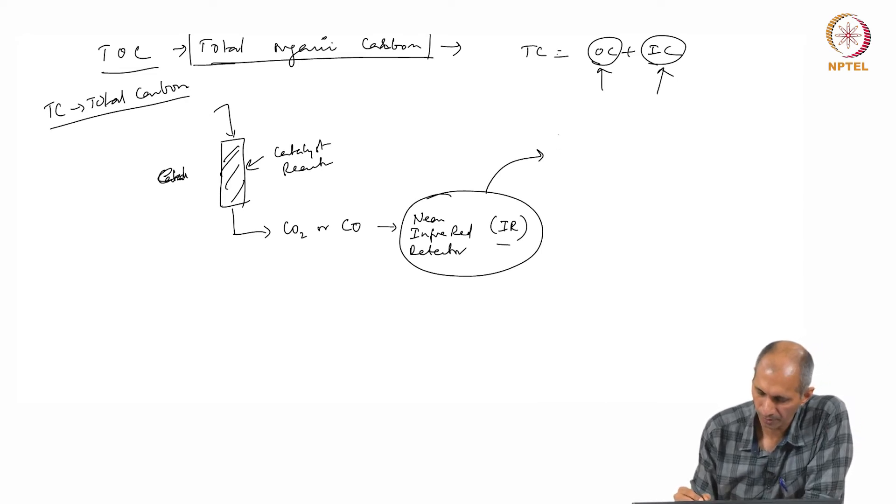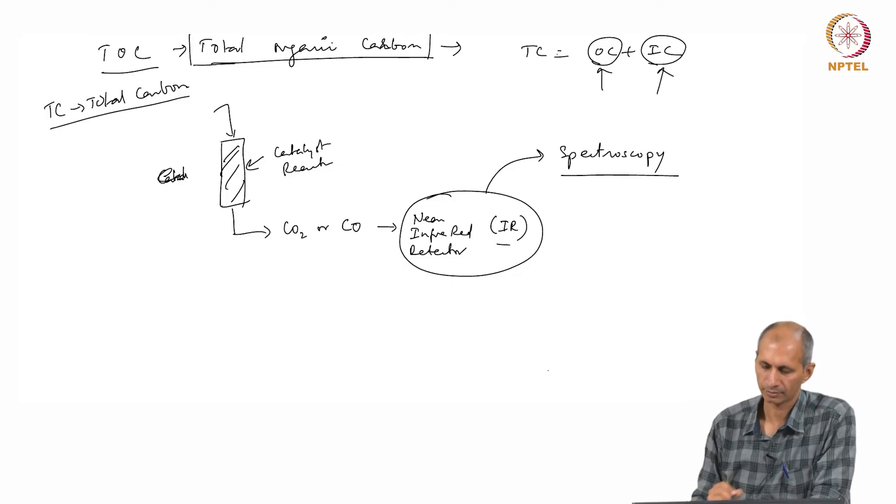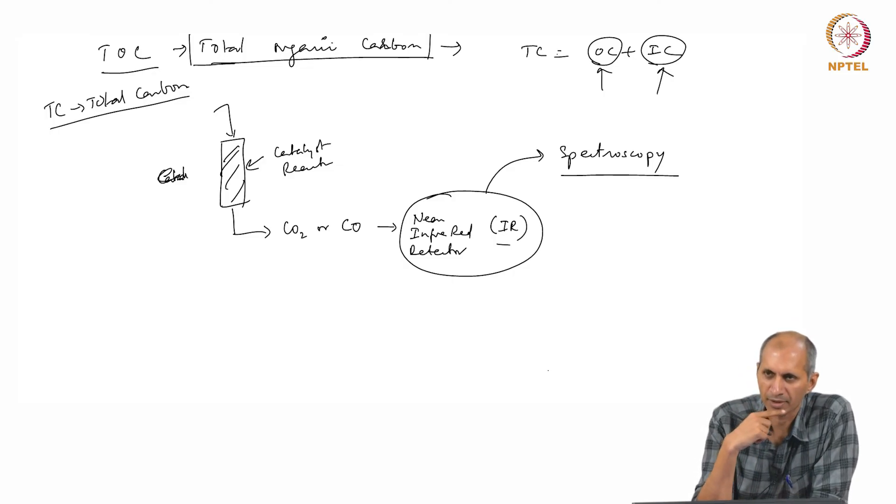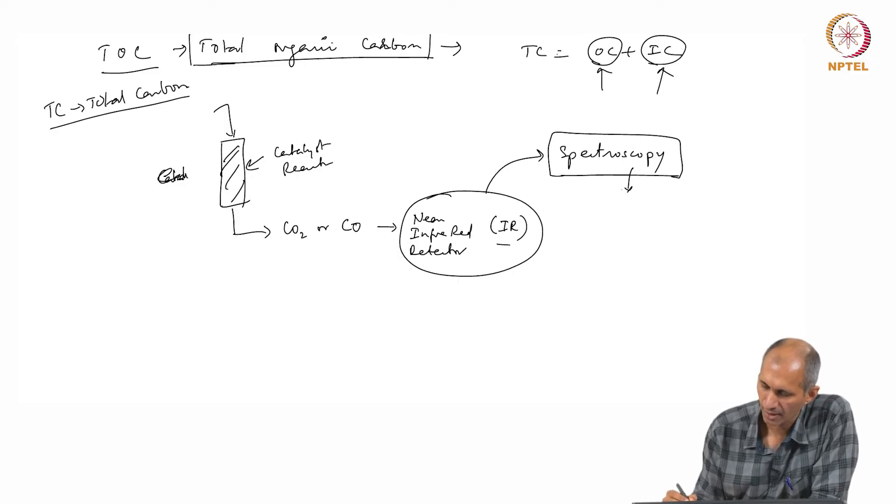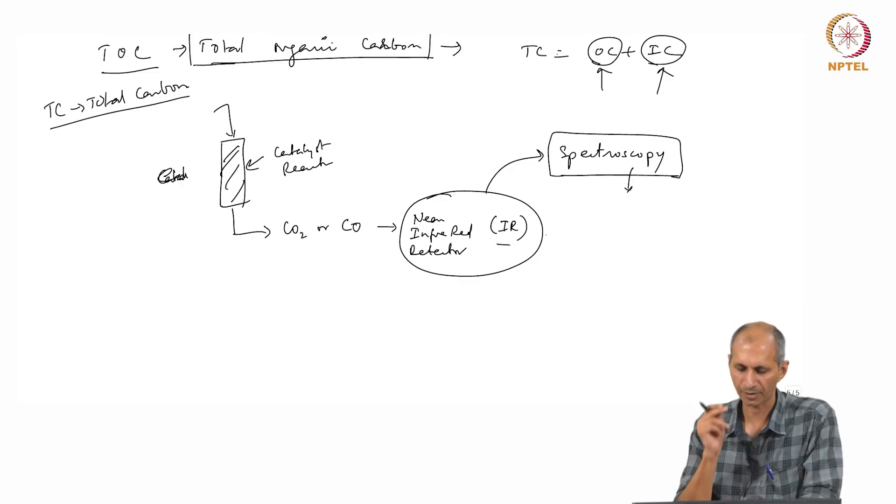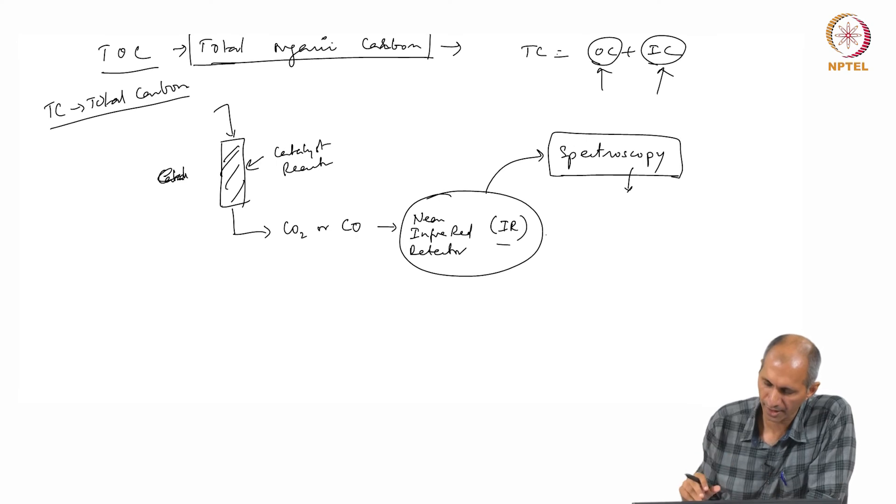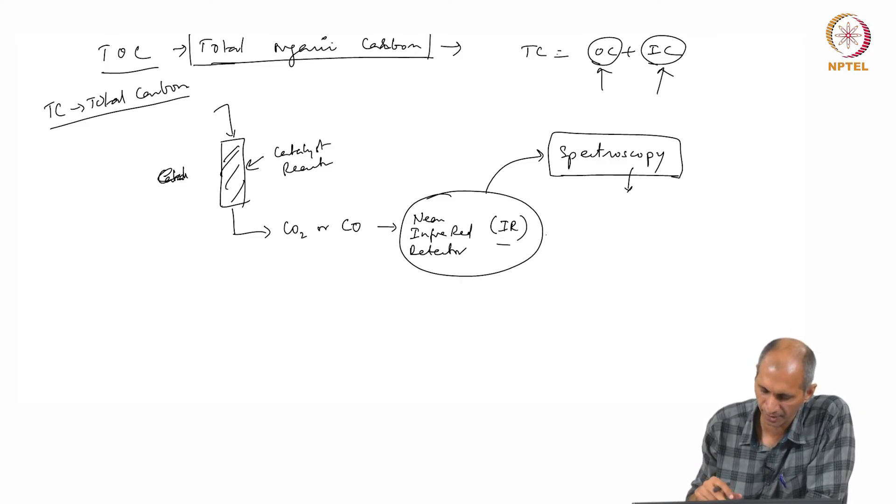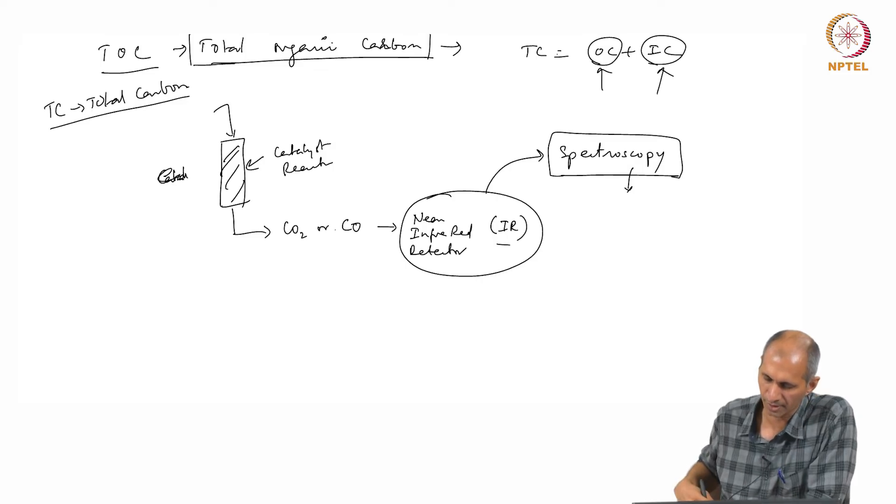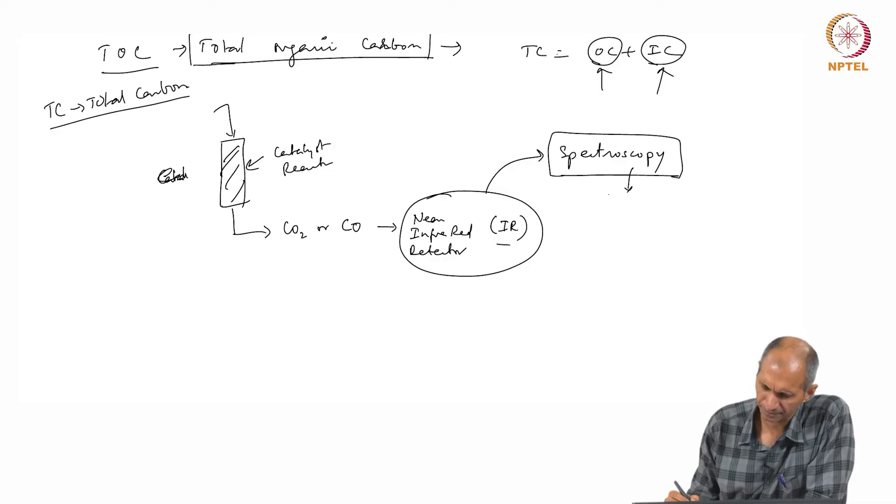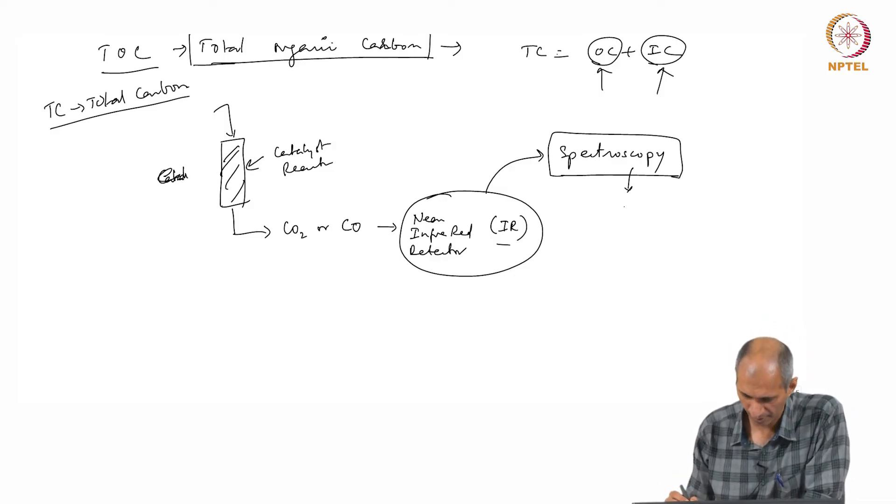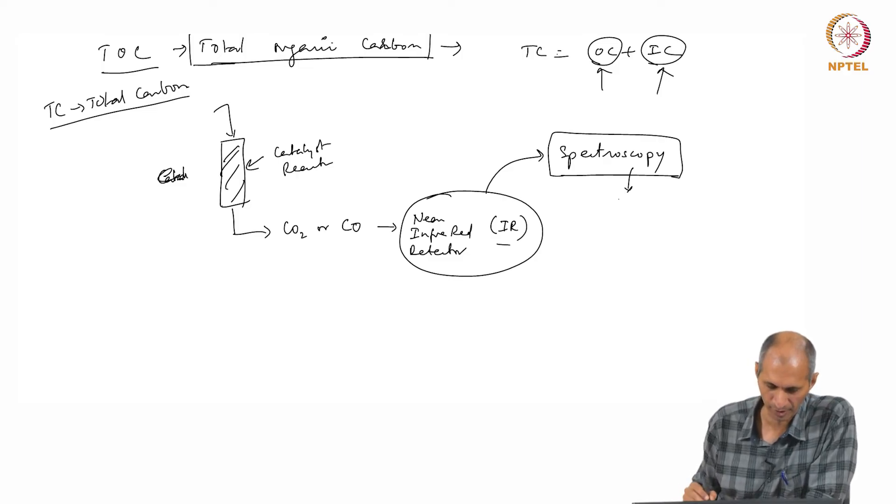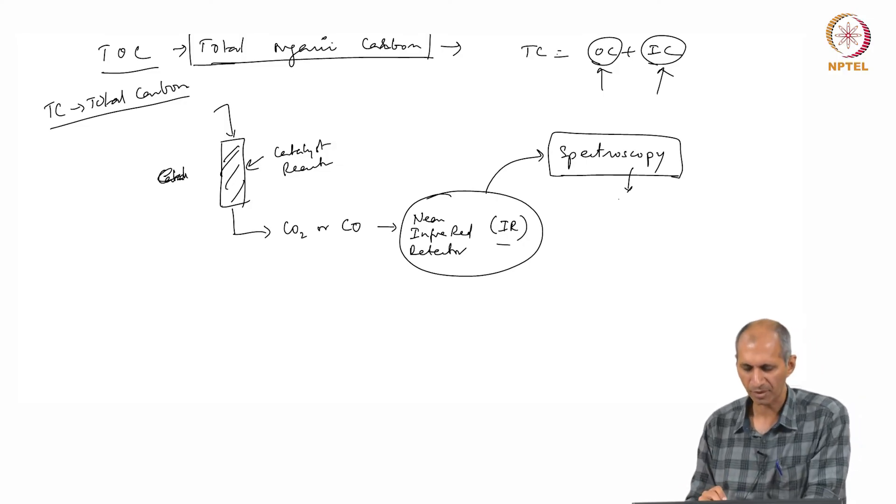This part I will explain a little bit later in the next section. This is what we call spectroscopy. There are different kinds of spectroscopies—atomic spectroscopy, molecular spectroscopy. We are using something where the material that is there interacts with radiation, in this case infrared. It interacts with infrared and gives some signal, and that signal is inferred in terms of CO2 or CO.